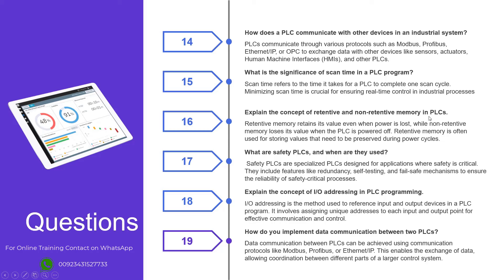Explain the concept of retentive and non-retentive memory in PLCs. Retentive memory retains its value even when power is lost, while non-retentive memory loses its value when the PLC is powered off. Retentive memory is often used for storing values that need to be preserved during power cycles. What are safety PLCs and when are they used? Safety PLCs are specialized PLCs designed for applications where safety is critical. They include features like redundancy, self-testing, and fail-safe mechanisms to ensure the reliability of safety-critical processes.